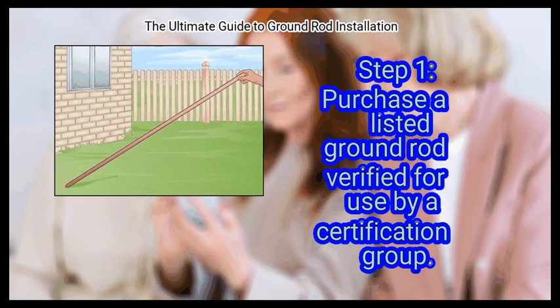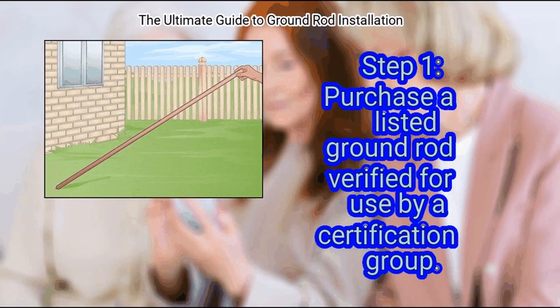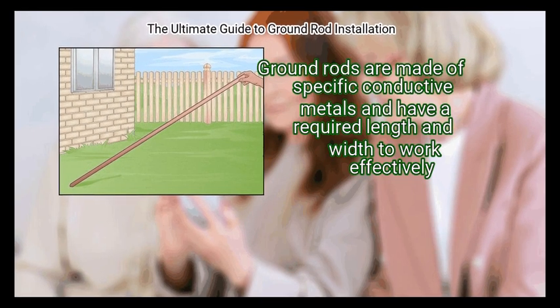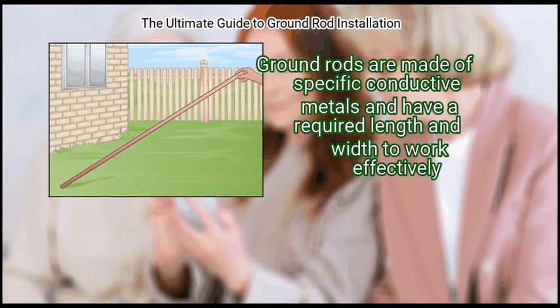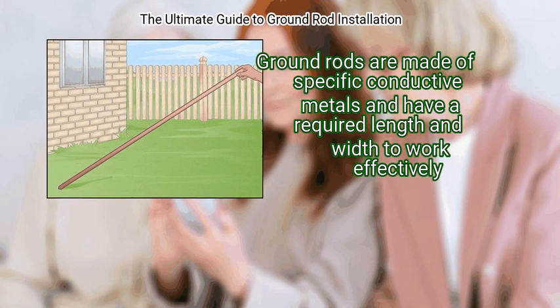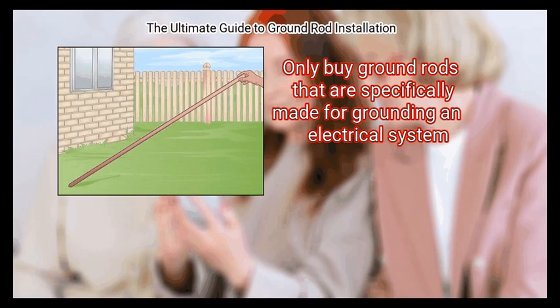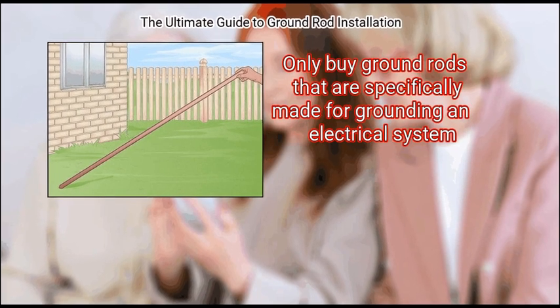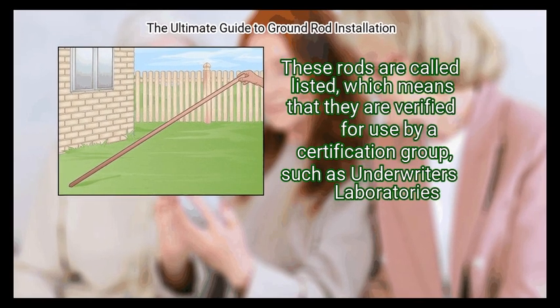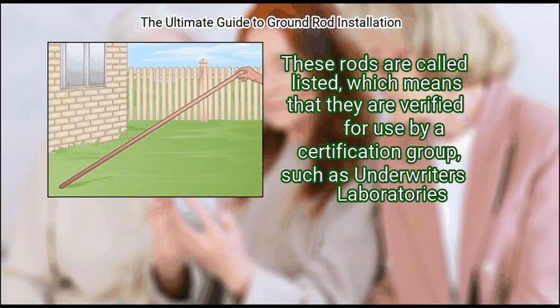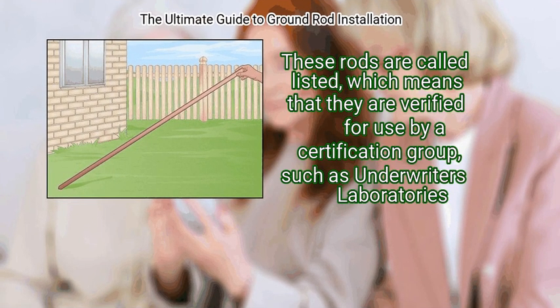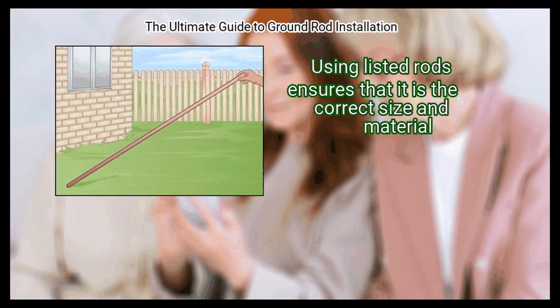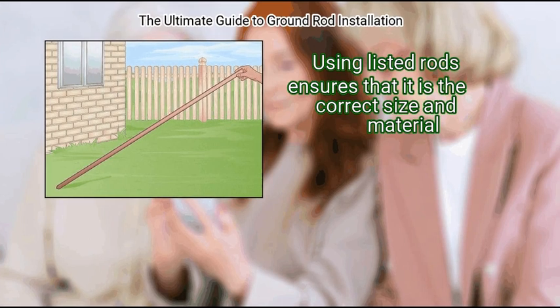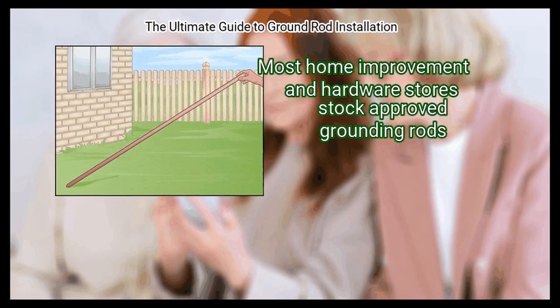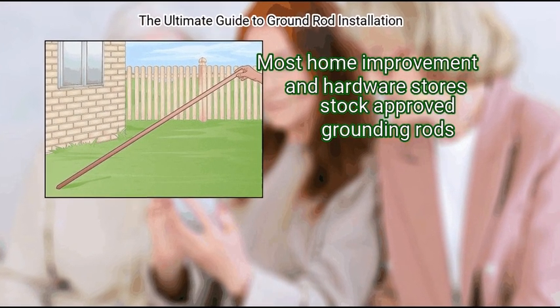First, purchase a listed ground rod verified for use by a certification group. Ground rods are made of specific conductive metals and have a required length and width to work effectively. Only buy ground rods that are specifically made for grounding in electrical systems. These rods are called listed, which means that they are verified for use by a certification group, such as Underwriters Laboratories. Using listed rods ensures that it is the correct size and material. Most home improvement and hardware stores stock approved grounding rods.